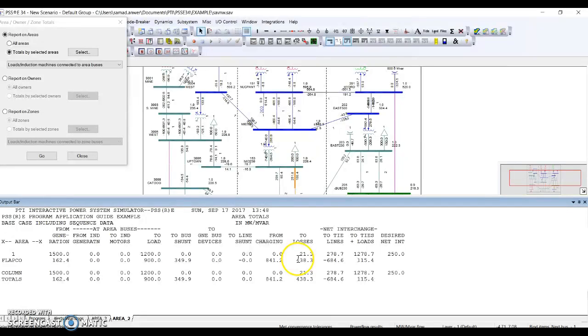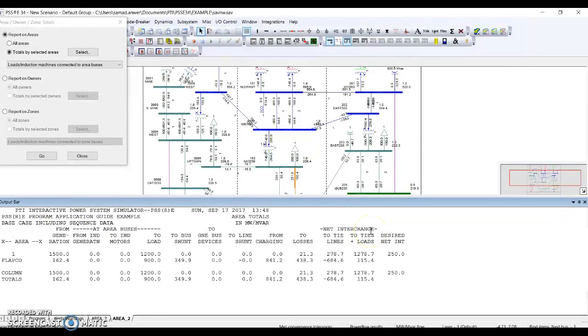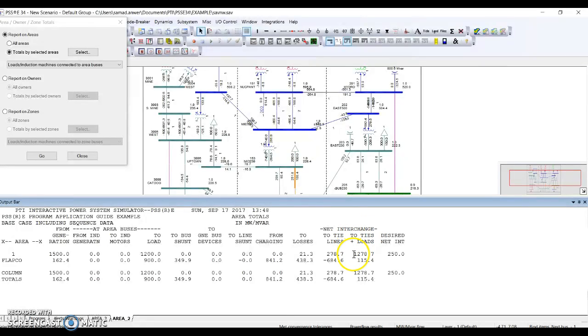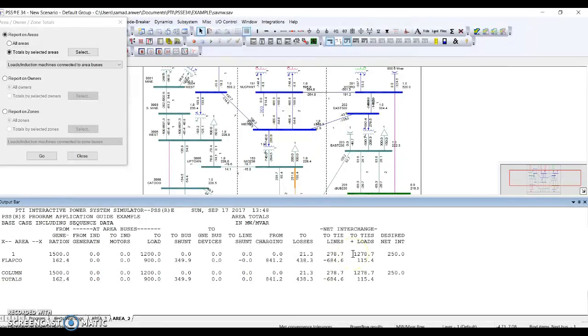And here on the right side of the report, the net interchanges shows the lines and how much I'm exporting. I'm exporting through two lines - 1278 megawatts. How do I know that I'm exporting? Because there is no negative sign before that digit. That means I'm exporting the power to other areas. So let's see what the other area shows.